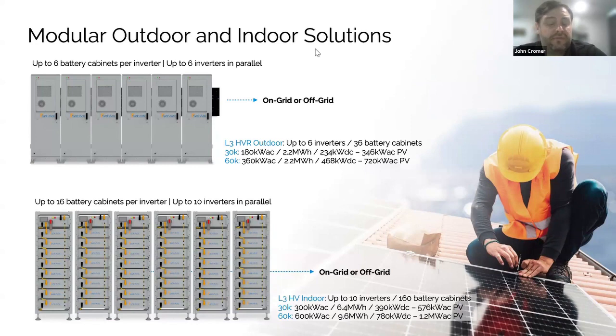Our containerized solution or our non-containerized solution has a very small footprint. One of the unique aspects is that the inverter is outside the battery cabinet, and that means the heat from the inverter is not inside the battery cabinet. A lot of our competition are taking inverters that were intended for server rooms, an air-conditioned space, a dust-free space, with a steady load, and they're just putting them inside a metal cabinet and calling it an outdoor rated ESS. Our inverters have many years of outdoor ruggedized testing behind them. They are intended for building backup power, not just backing up steady loads.